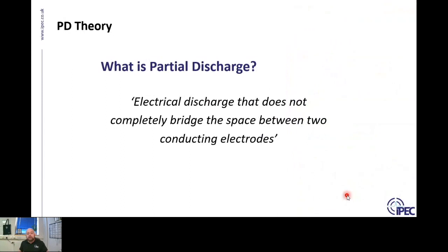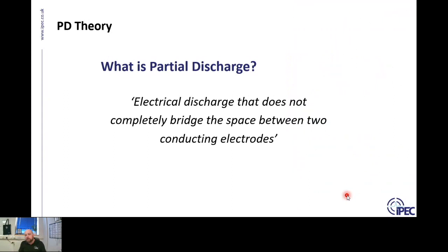Let's begin. What is partial discharge? Many of you may be familiar with partial discharge in other types of electrical assets in your network, and cable PD is exactly the same. Partial discharge is an electrical discharge that doesn't completely bridge the space between two conducting electrodes — so with insulation between the core of a cable and the earth sheath, the discharge is not occurring completely across that gap.